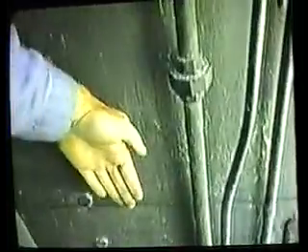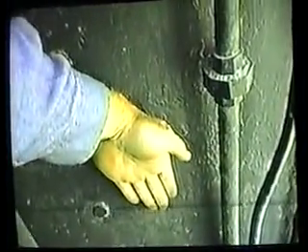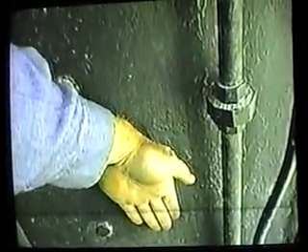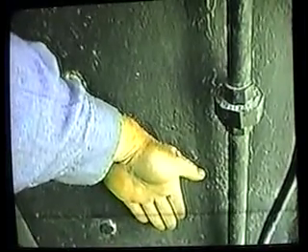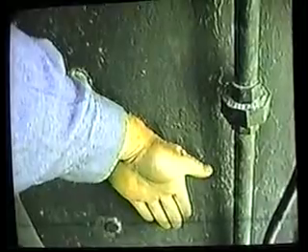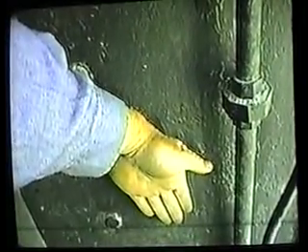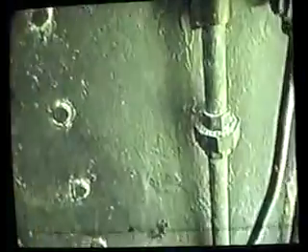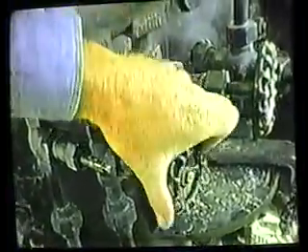Check the temperature of your oil in the tank with the back of the hand. If it's uncomfortable to the back of the hand, then your oil is getting too hot. You shut down the tank heater. You want to open the atomizer valve for a few seconds to blow out any condensation that may be in the burner.